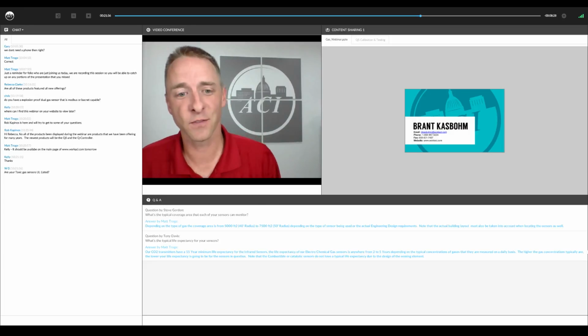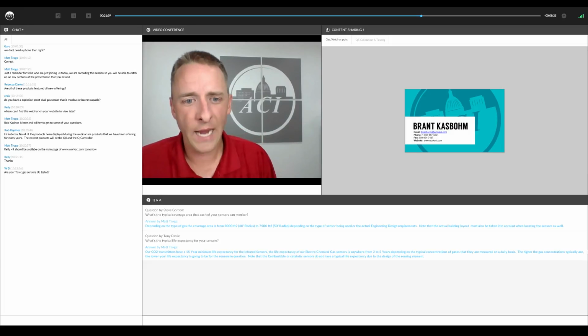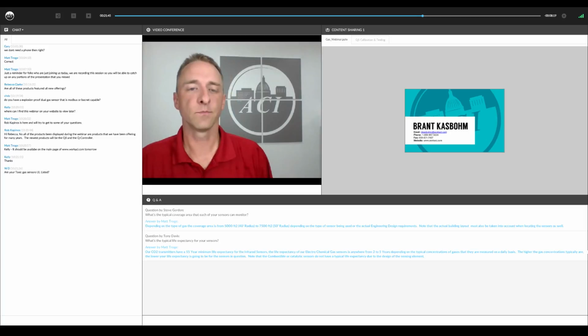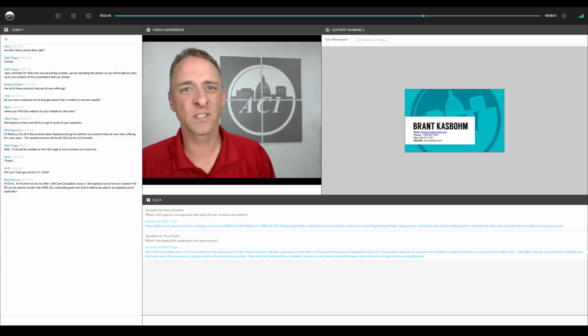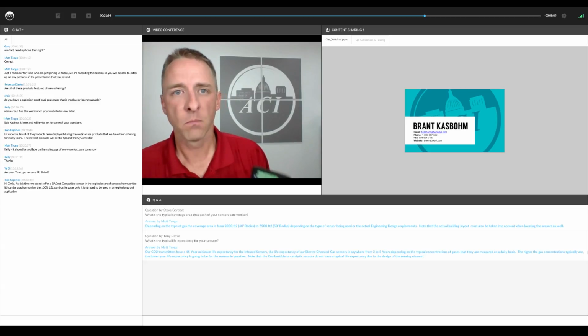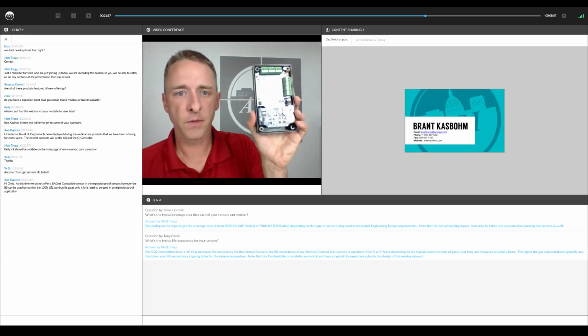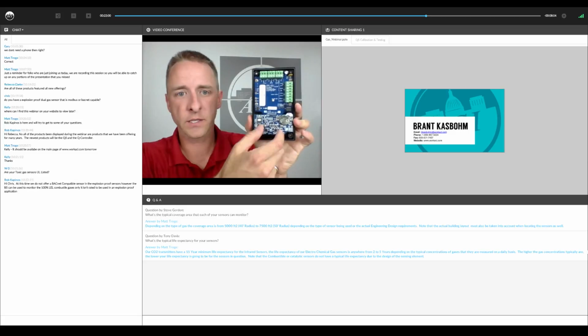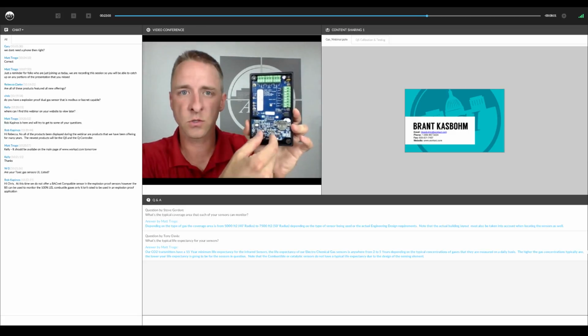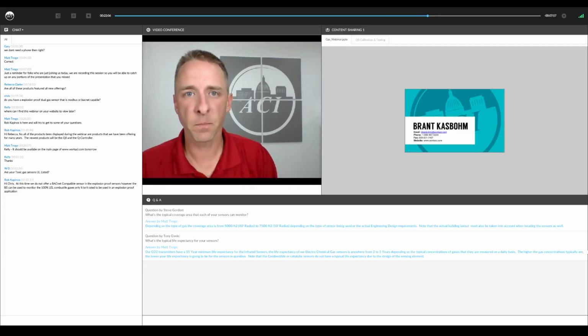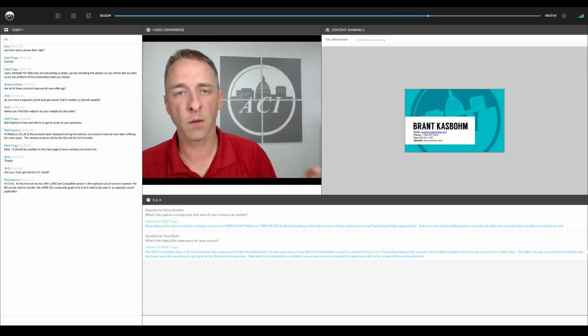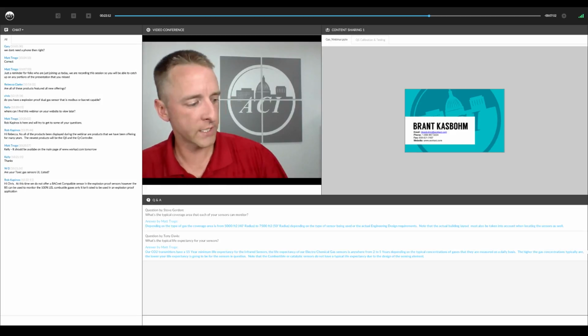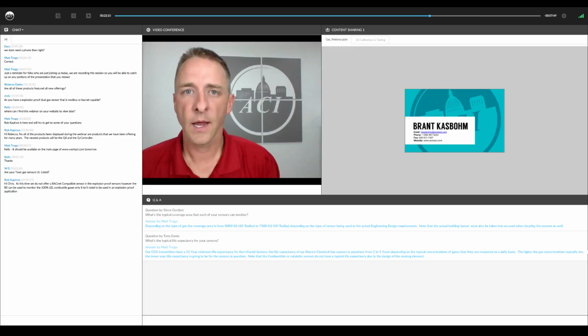Can your gas transmitters have the sensors replaced in the field? Yes, I should say yes for some of them. For CO2, no, those sensors are not replaceable. But for our toxic and combustible gas sensors, most of them are field replaceable. For the Q5 and B5, it's a very simple process to snap in a new sensor. There's 2 small screws that hold the sensor onto the back of the circuit board, and it snaps right in, and it comes pre-calibrated. But for CO2, that sensor doesn't wear out over time, and there's no need for a field replacement of a CO2 sensor. Most of the gas sensors can be field replaced.